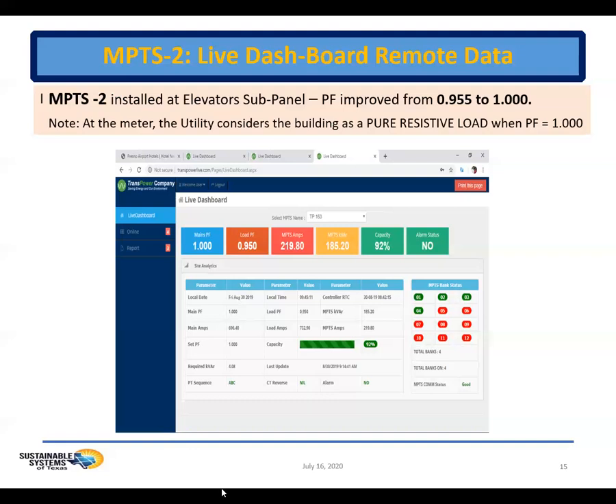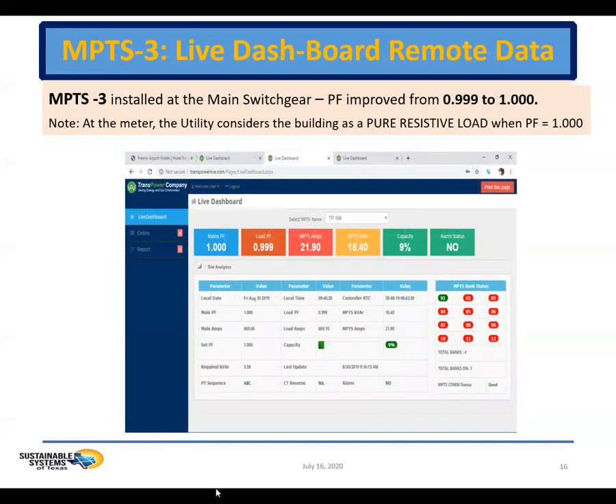So now let's look at MPTS 3, which is installed at the main switchgear. Here we can see it recording the load power factor at 0.99 and the main power factor at unity. This MPTS is only at 9% capacity. So why is this? Because the 2 other MPTS units on the subpanels are cleaning up the building power, and at this moment, the incoming utility power at the main is relatively clean. From the top line of the dashboard, note also that the MPTS amps are almost the same before and after. So why is that?